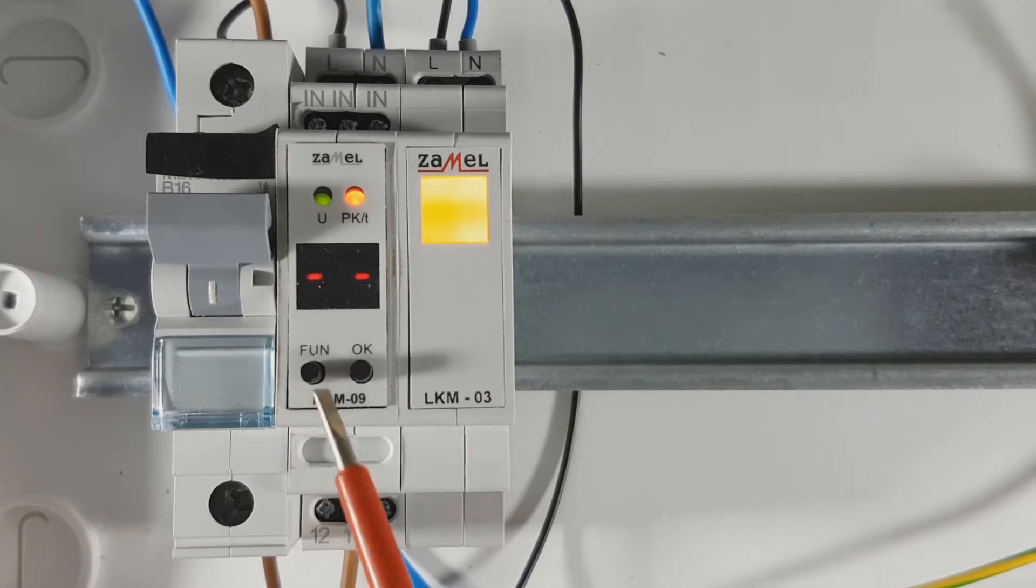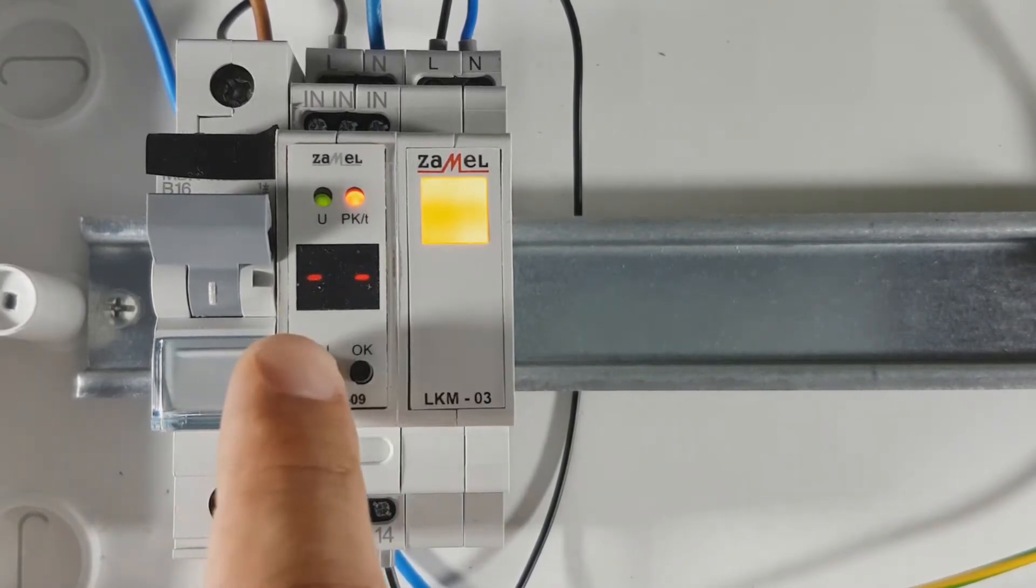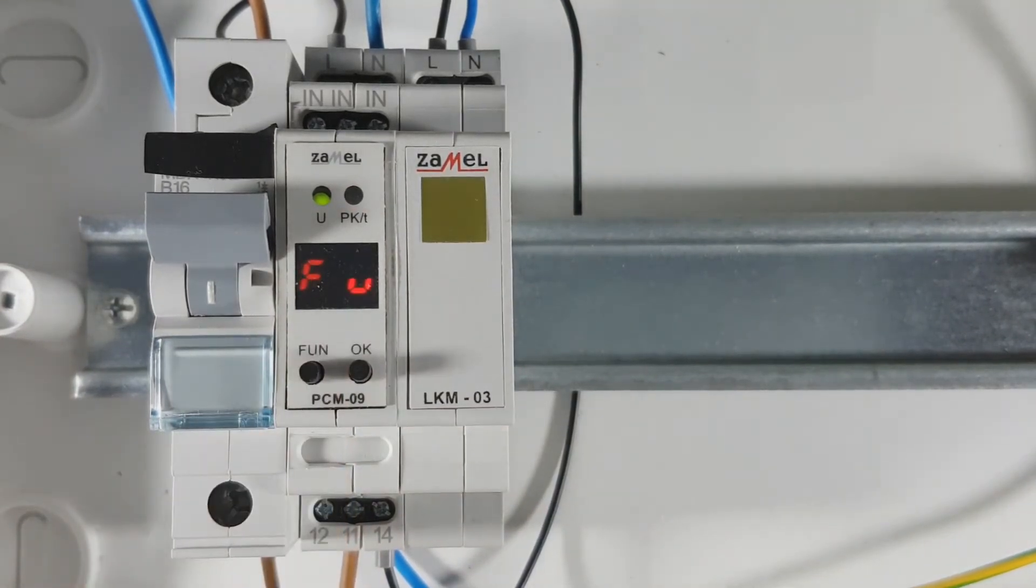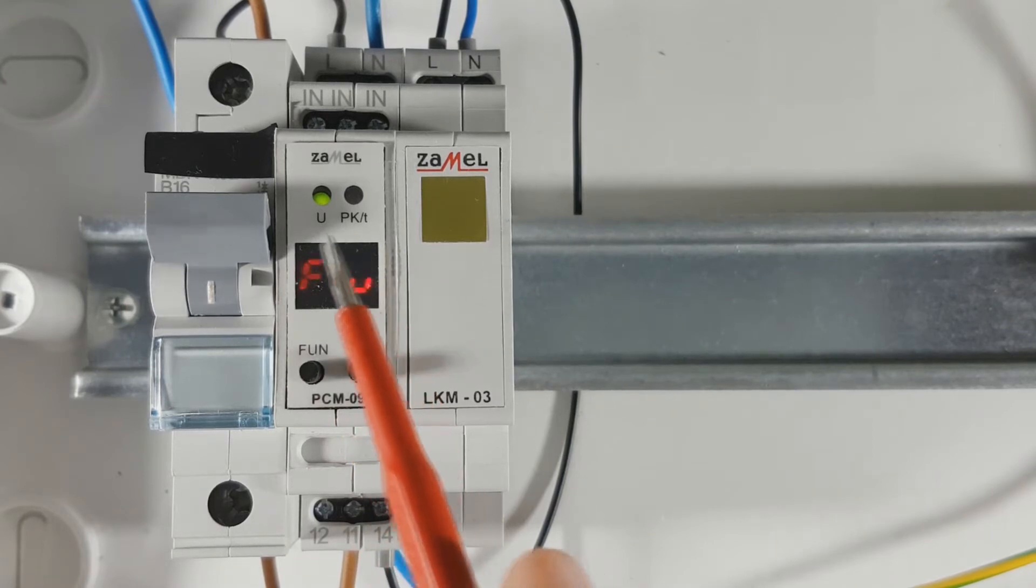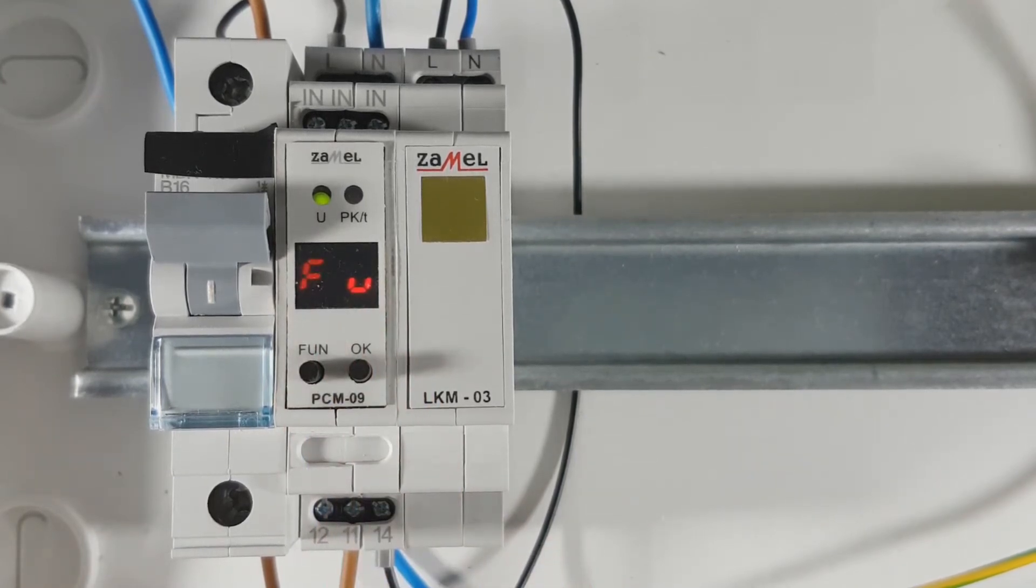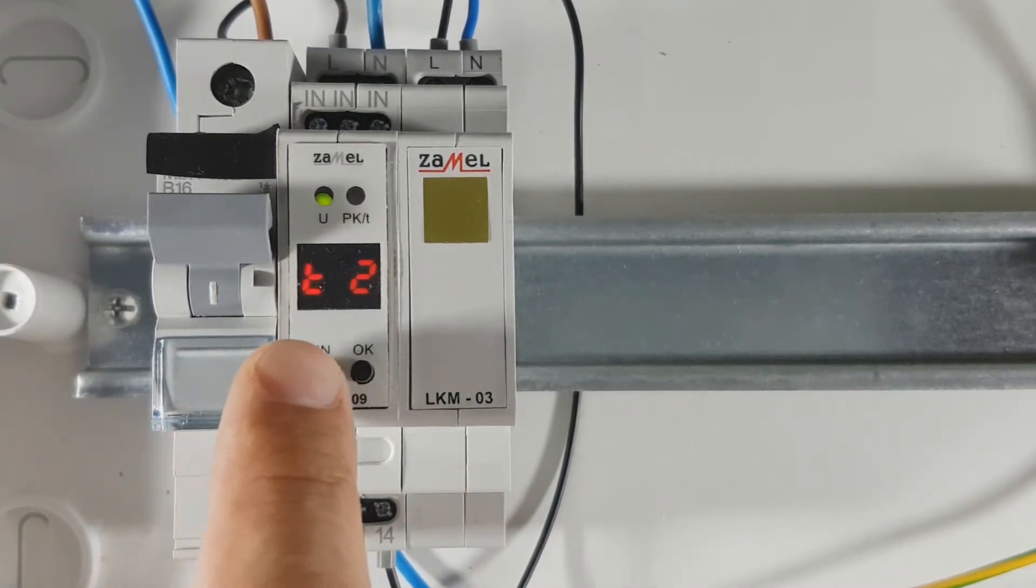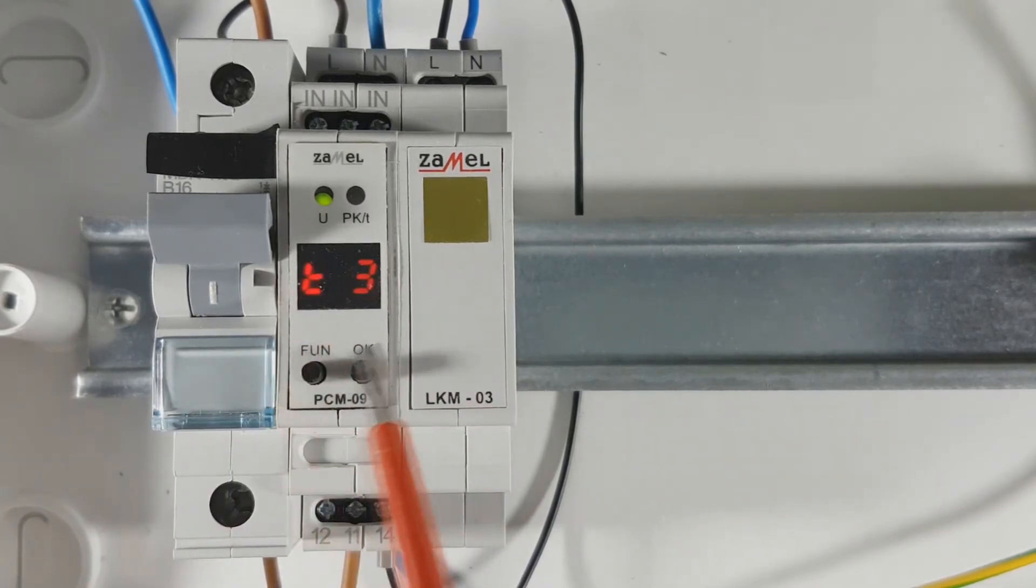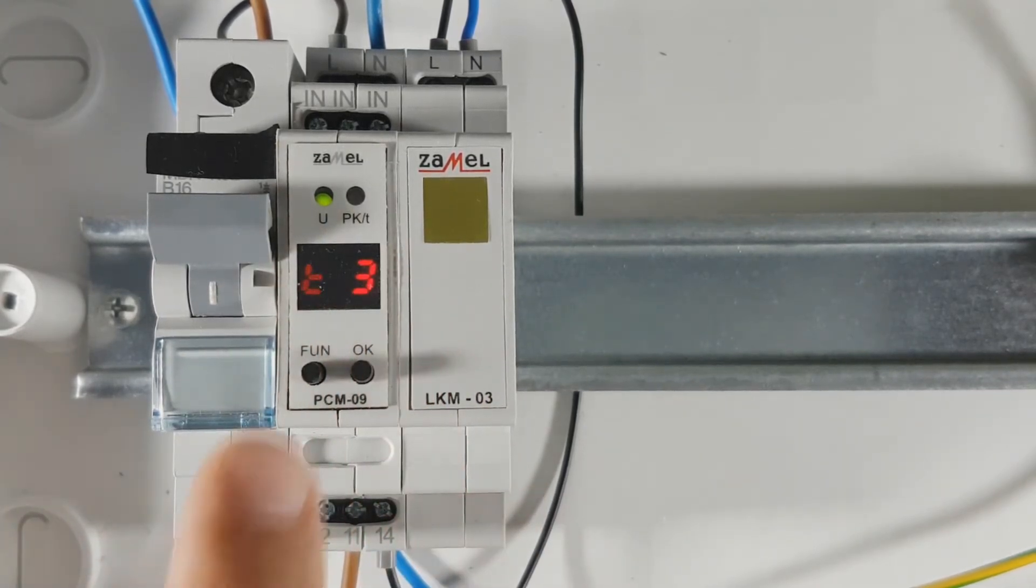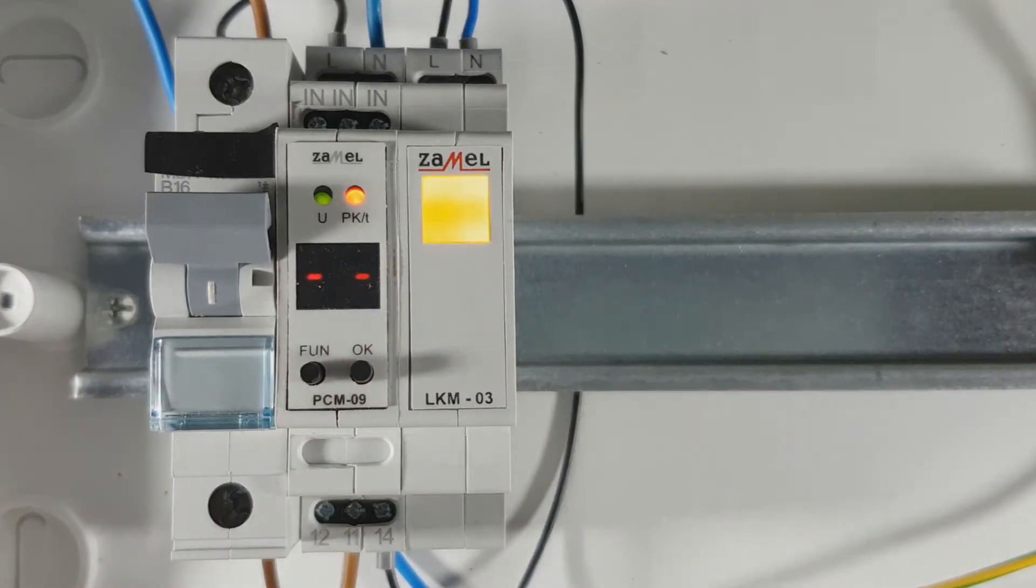In order to set the device, press the function key for about 3 seconds. The display shows available operating modes of the relay. The next press of the function button selects the times: accordingly, T1, T2, or T3 time. The following next press of the function button quits the programming mode and begins regular device operation in the selected mode.